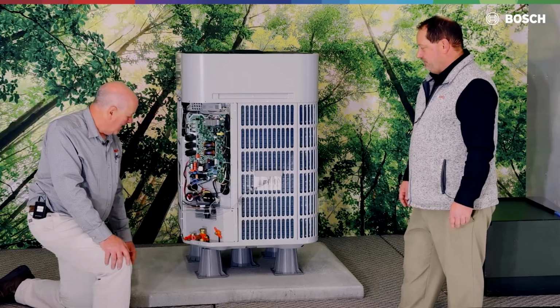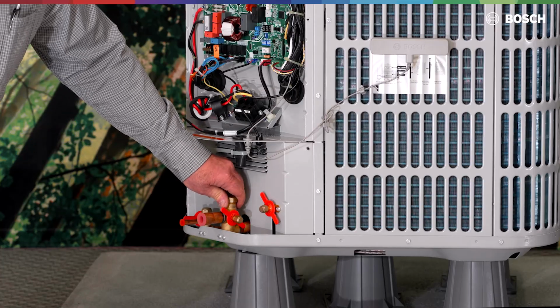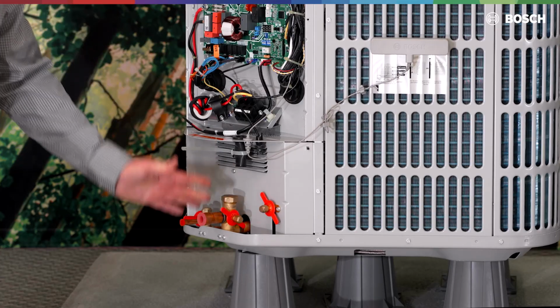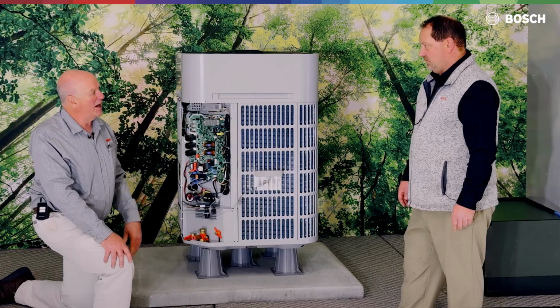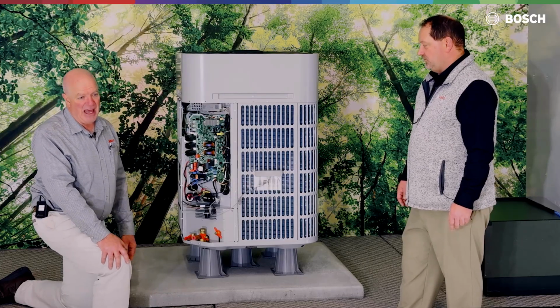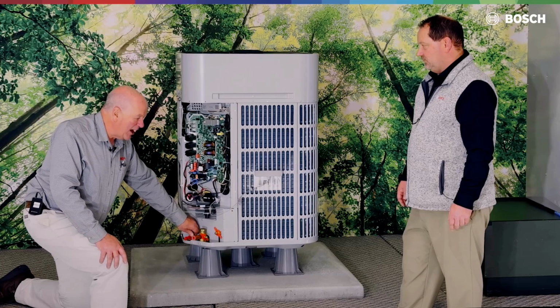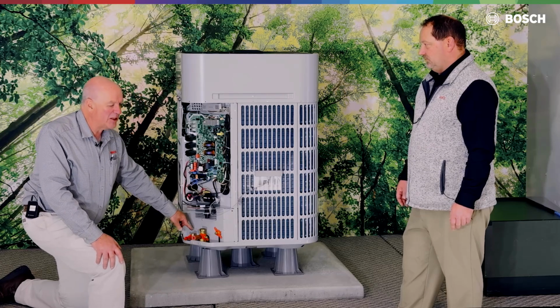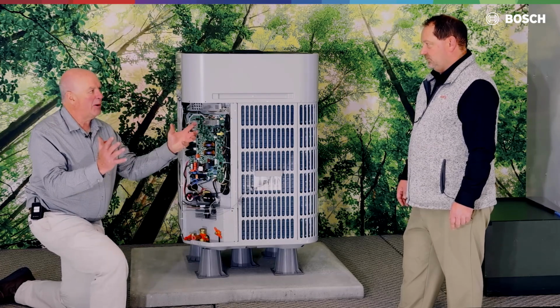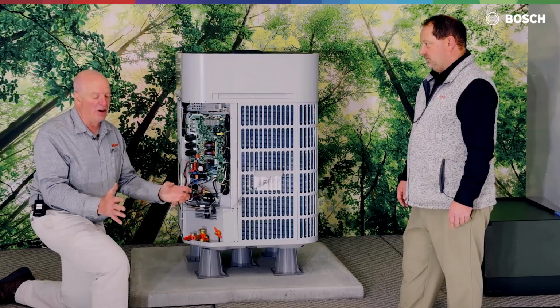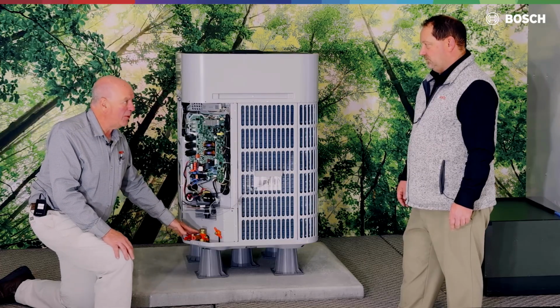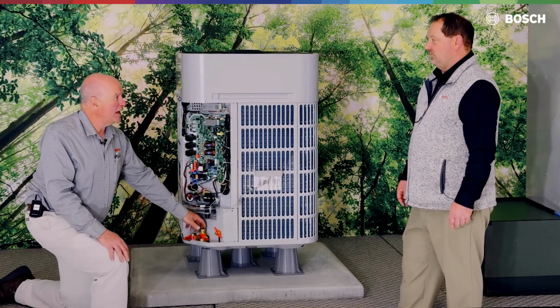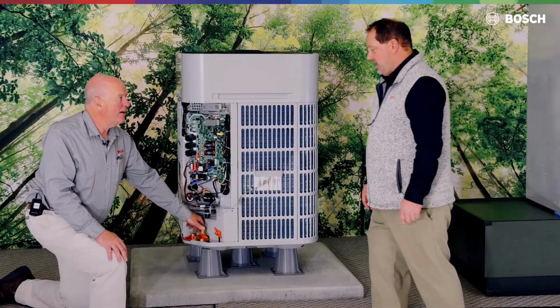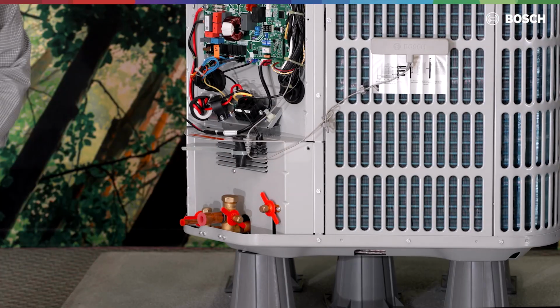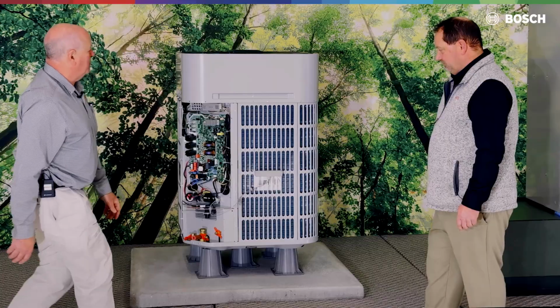But please don't take this thing and run it up crazily and all of a sudden the valve blows out and say, hey, we got a defective valve. That doesn't happen. If you go to crack this valve and you back off, you backseat the valve, and refrigerant starts to blow out of the valve, that is a defective valve. If there's just 1 or 2 slight bubbles, that's not an issue of concern. Cap it. These are machine fit. They should seal up and have no issues at that point. Great point, Chris.